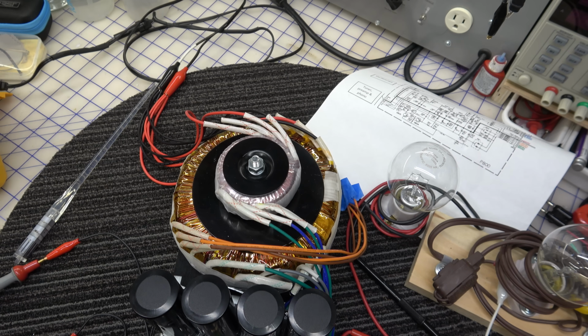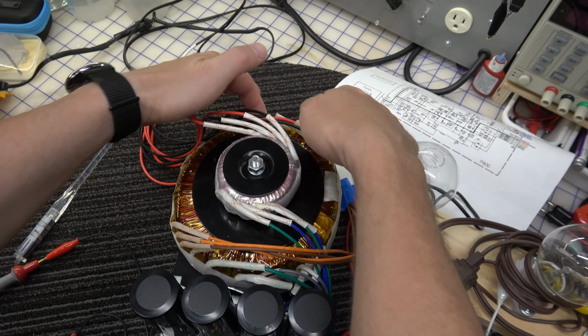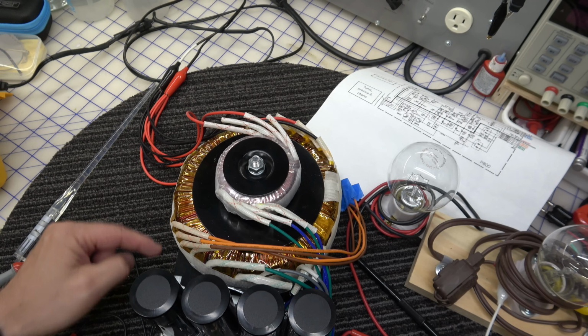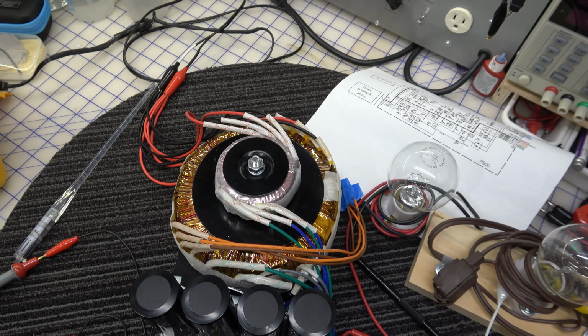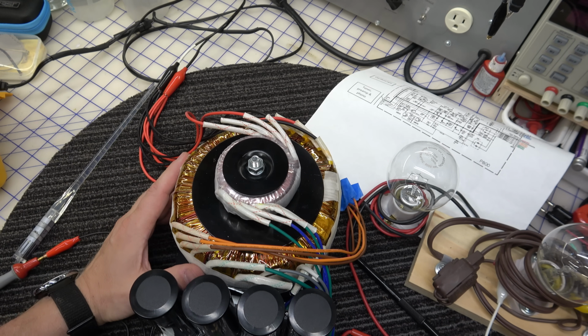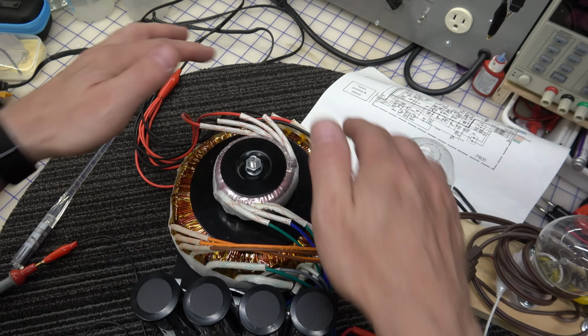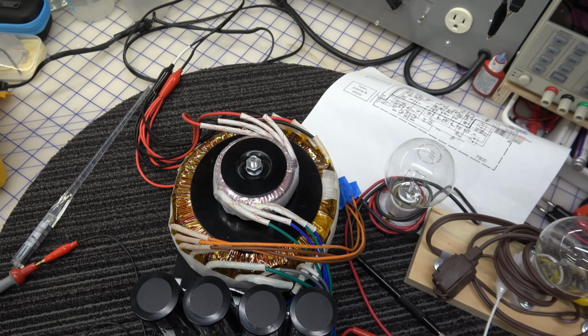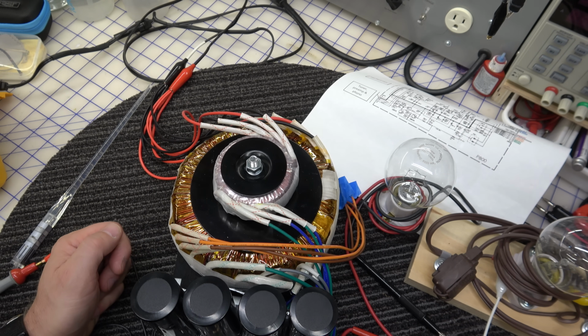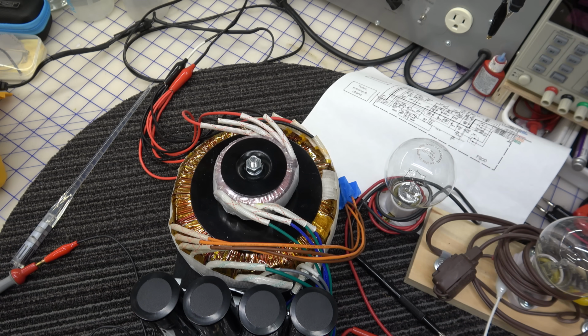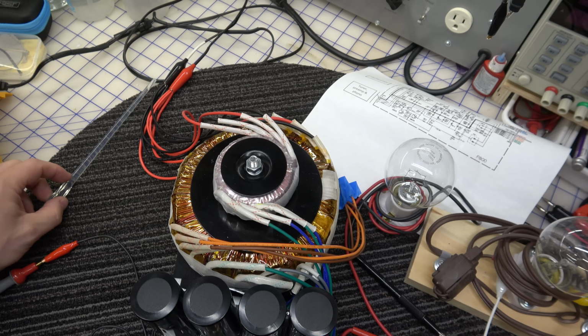If you're trying to suppress the H field or magnetic field of the transformer, putting a piece of copper tape around it and grounding it isn't going to do a thing—it'll go right through that. However, if you're trying to keep this transformer from capacitively coupling from something, then putting a copper shield around it and grounding it would help suppress that capacitive coupling. So the shielding strategy depends on, number one, the transformer type, and number two, which field you're trying to suppress.